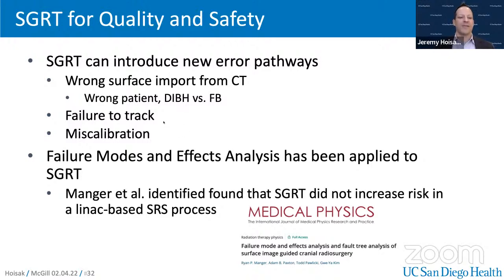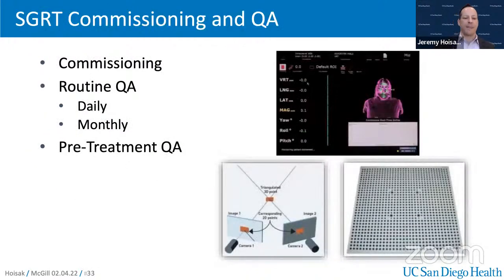Another potential error pathway is failure to track. You could have your SGRT system tracking the patient, and the patient is moving, but the system is not updating to show that movement. Failure to track is actually a major failure mode that was identified in this work by Manger et al. He's my colleague at UC San Diego. They did an FMEA for SGRT applied to SRS, and they found that SGRT did not significantly increase the risk when using it for a LINAC-based process.